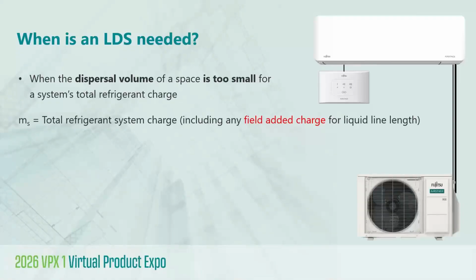So although today's focus is going to be on LDS devices, it is helpful to briefly review when an LDS is required. In simple terms, an LDS is needed when the dispersal volume of a space is too small relative to the system's total refrigerant charge. Keep in mind, the total refrigerant charge is a function of the factory pre-charge as well as any additional refrigerant that's added for extended liquid line lengths.